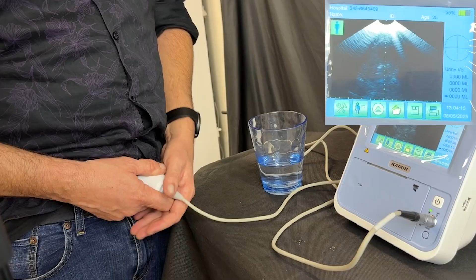What we want to do is get the line. You can see a dotted green line here on screen. We want to get that as close together in the middle of that black void as we can. And that's going to give you your most accurate scan. The machine will tell you if it's an accurate scan as well.